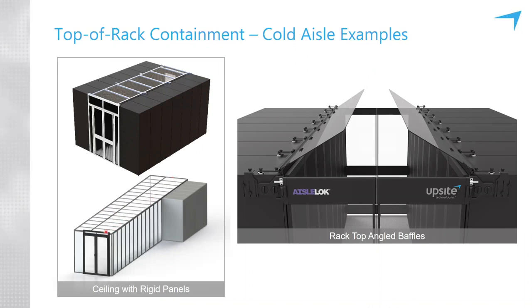These panels can be configured to fit the width of any aisle. Also in this rigid containment example, just a little side note, panels can be constructed that are the size of each cabinet so that if you wanted to add one cabinet here, this panel could be removed and one cabinet could be rolled in, a way to maintain full containment throughout the growth of the deployment of cabinets.